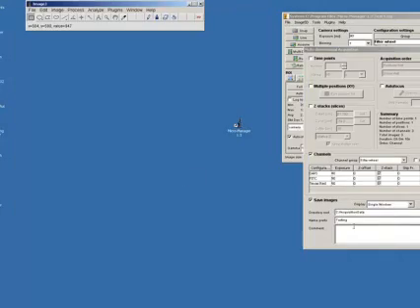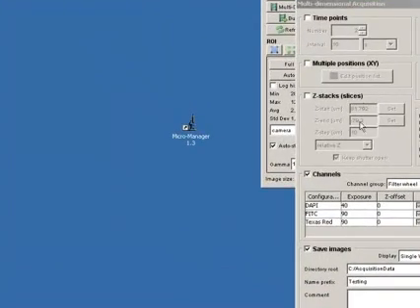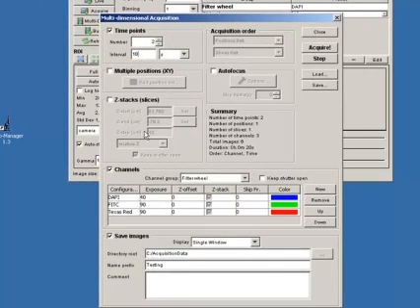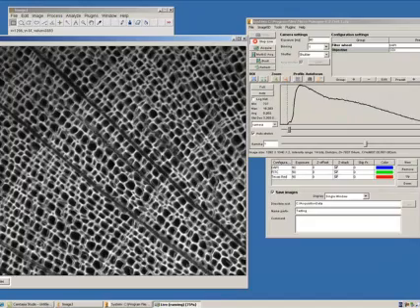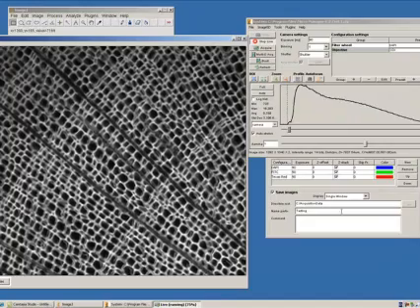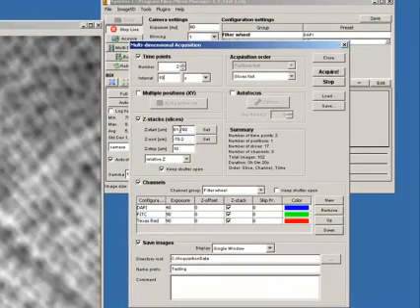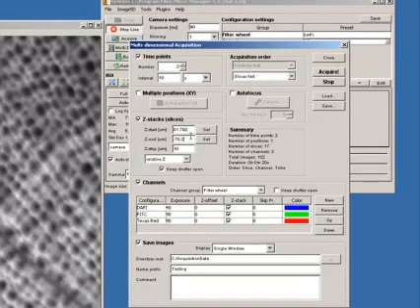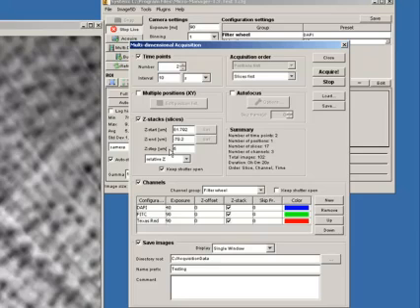So, if I wanted to now add in let's say time points. I just tick time points and enter in the number of time points I want. So, let's go for 2. And we'll have an interval between acquisitions of 10 seconds. It's fine. Next, if I wanted to include Z stacks. Then we just need to tick the Z stack option here. And we can go live for a moment. And we can define the top and the bottom of the stack. So, let's roll up through focus a little bit. And set that one. And then roll down through focus. Set the bottom. And then you can enter in the number of slices you want. So, let's go for 5.